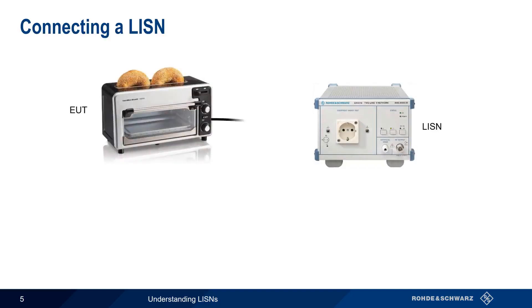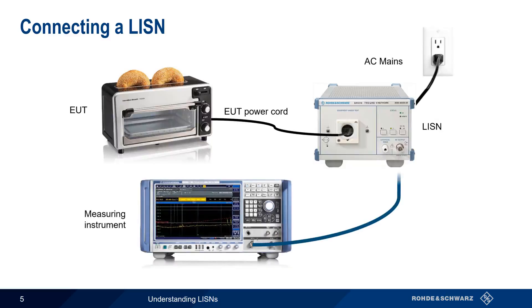Let's look at how a LISN is connected when making a conducted emissions measurement. The EUT's power cord is plugged into the LISN, and the LISN is plugged into the AC mains network. Our measuring instrument — here, an EMI receiver — is plugged into the LISN's measurement port in order to measure the levels of conducted emissions.